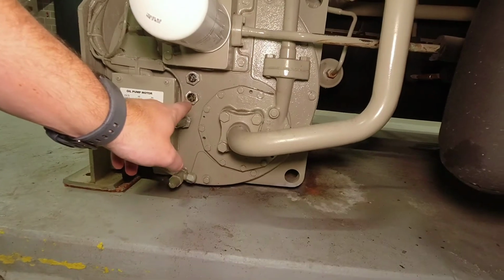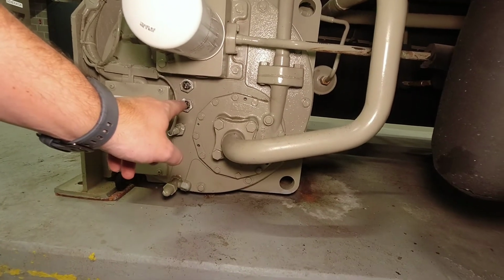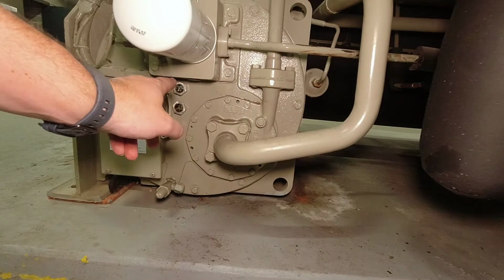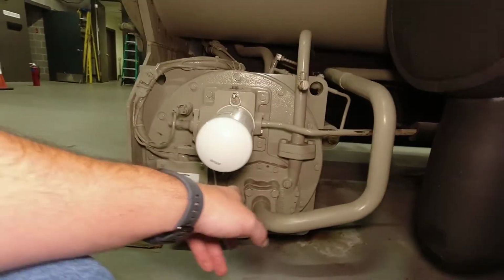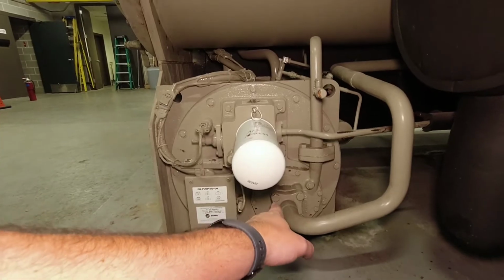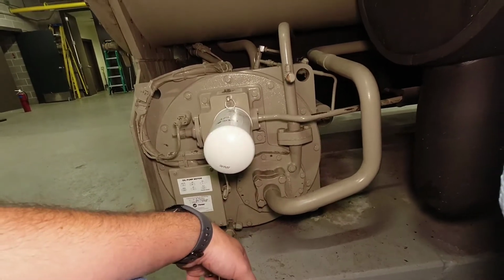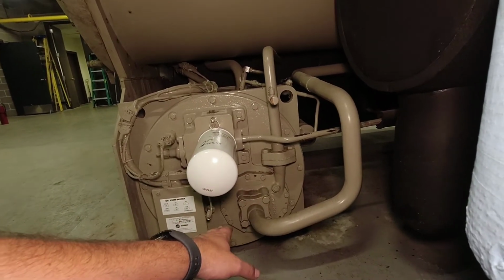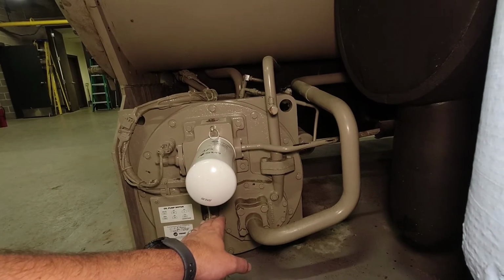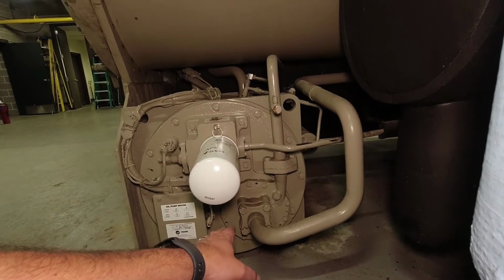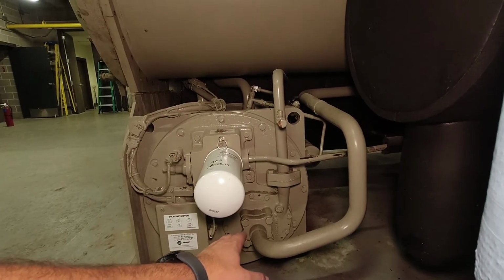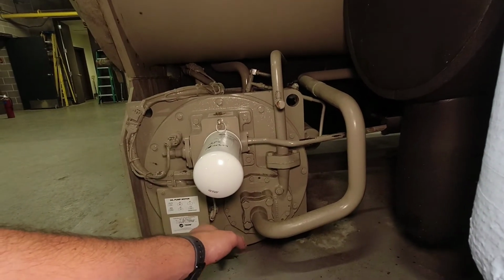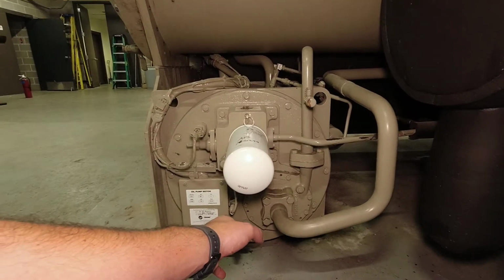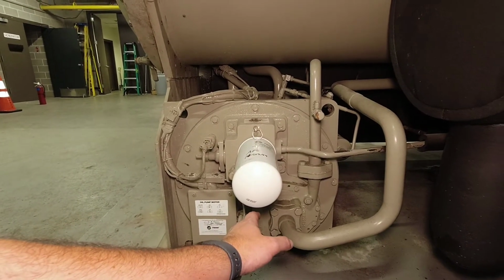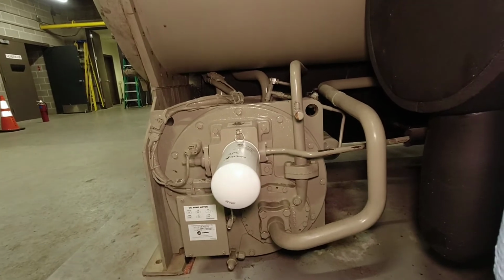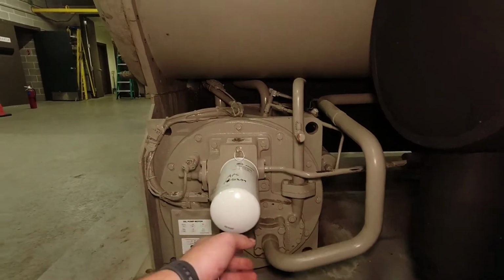I like to keep my sight glasses either between them, or I really prefer to be up into the upper sight glass. That is my preference. I like to maintain there to make sure we've got enough oil. If I get down into the lower sight glass, when I start seeing it there, I usually start recommending to the customer that we need to see if we're losing oil, or if we're having a migration issue, or what's going on, and then possibly adding oil if needed.